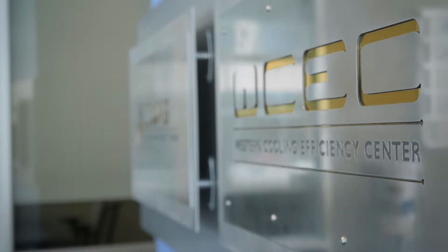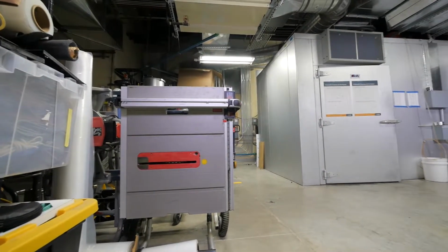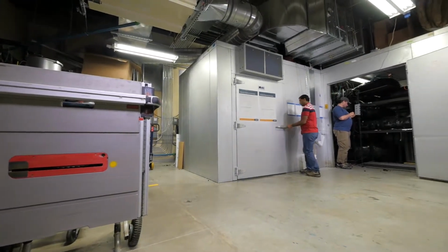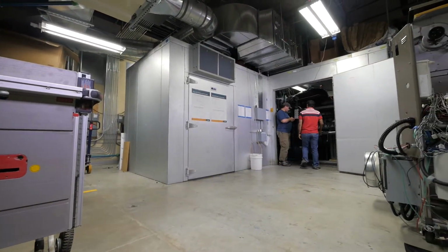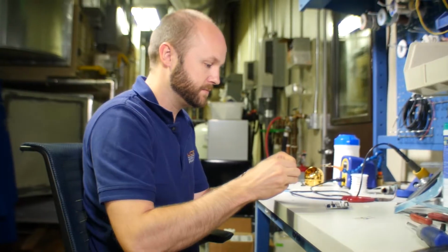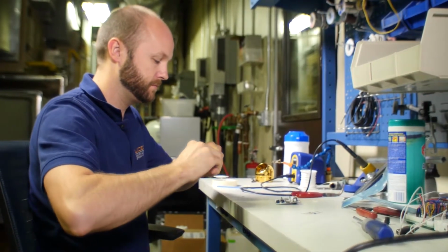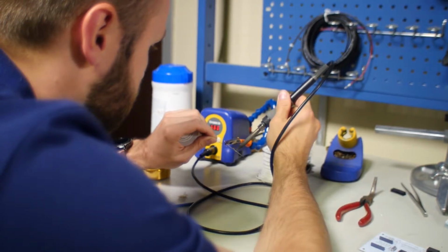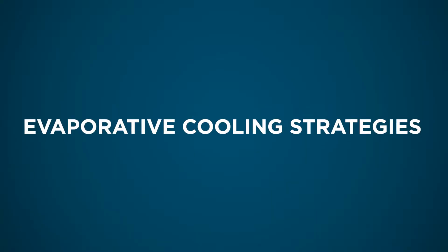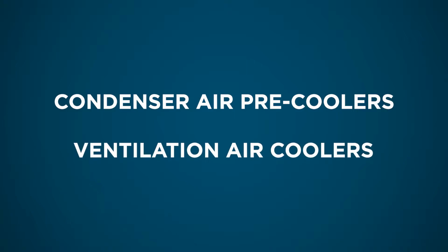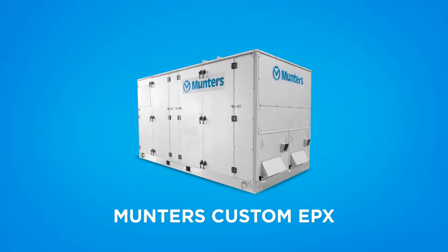One such third-party testing facility is the UC Davis Western Cooling Efficiency Center, or WCEC, the makers of this video. The WCEC researches, develops, and demonstrates technologies, including evaporative cooling technologies, that address both overall energy consumption and peak demand. A variety of evaporative cooling strategies exist for commercial buildings, and they can be categorized into two broad groups: condenser air pre-coolers and ventilation air coolers. This video will explain one evaporative cooling product called Munters Custom EPX.